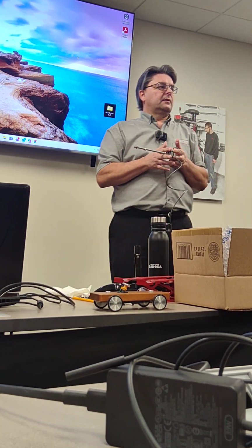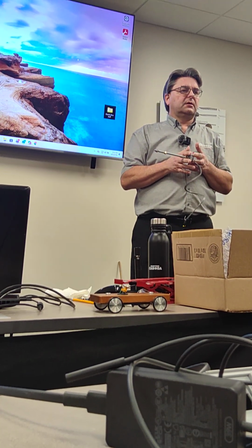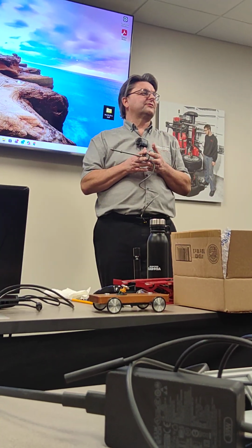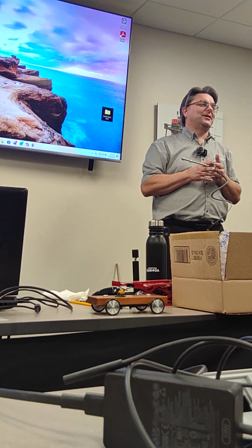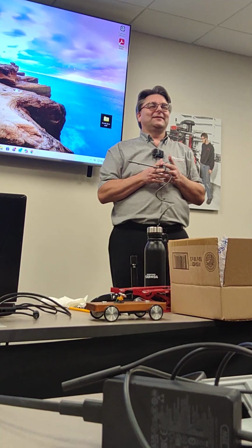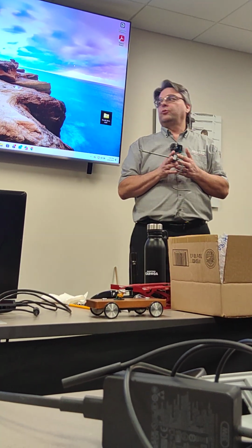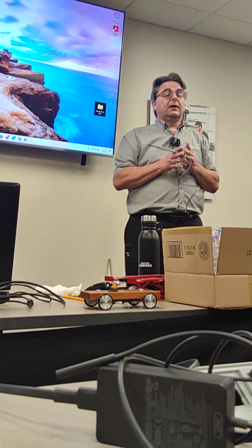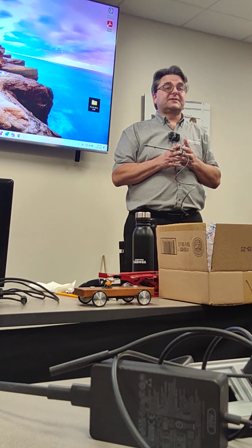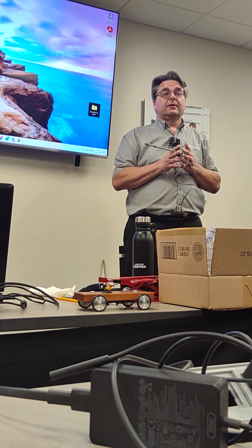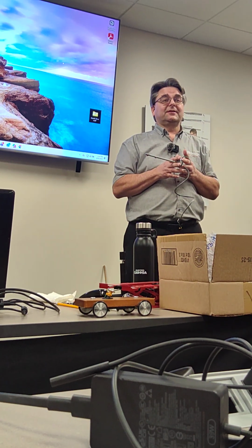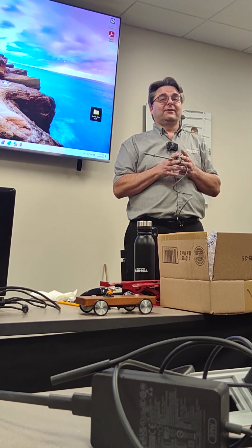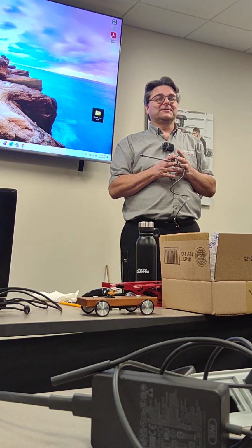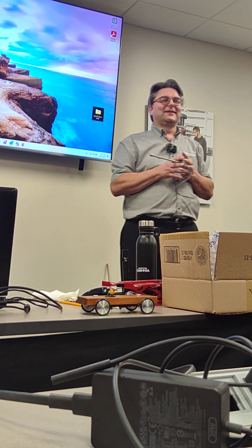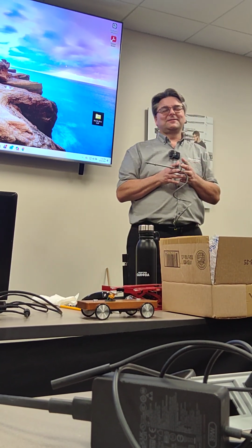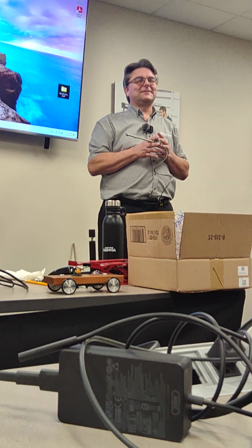No, those are foot-pounds. Foot-pounds, inch-pounds, right? Inch-pounds. We don't have inch-pound torque wrenches here, so figure out what 70 inch-pounds feels like to you. Basically, it's snug, and then you go, ugh, and you're at 70 inch-pounds. That's about 6 foot-pounds.